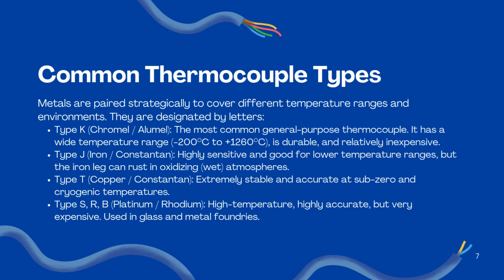Next is type T, copper and constantan, extremely stable and accurate at sub-zero and cryogenic temperatures, which is below zero. Type S, R and B, which are platinum and rhodium, are high temperature and highly accurate, but very expensive. Used in glass and metal foundries.